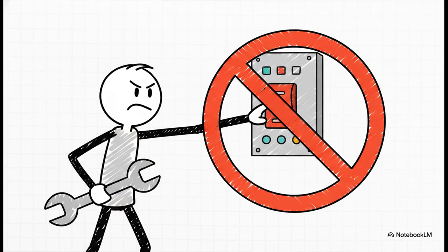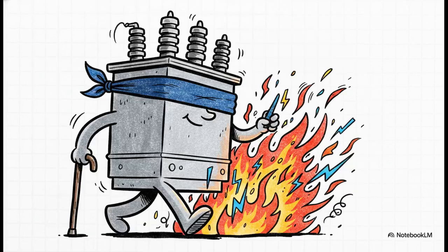Because this protection is so vital, there is a golden rule in the field. I cannot stress this enough. Never, under any circumstances, disable harmonic restraint settings just to fix a nuisance trip. When a system keeps tripping during startup, the temptation for a frustrated commissioning engineer is just to turn off the second harmonic restraint to force the machine to run. Doing that is incredibly dangerous.